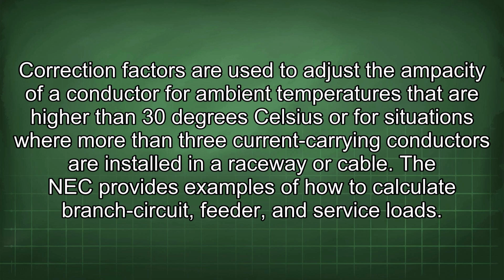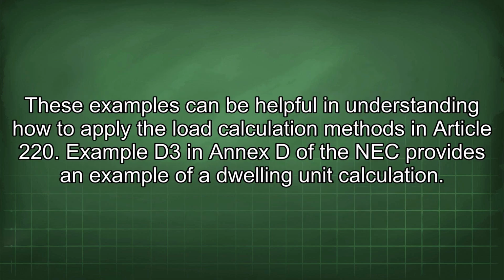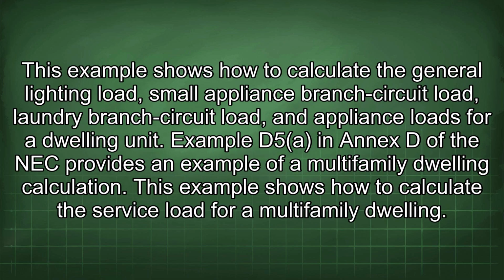The NEC provides examples of how to calculate branch circuit, feeder, and service loads. These examples can be helpful in understanding how to apply the load calculation methods in Article 220. Example D3 in Annex D of the NEC provides an example of a dwelling unit calculation. This example shows how to calculate the general lighting load, small appliance branch circuit load, laundry branch circuit load, and appliance loads for a dwelling unit.